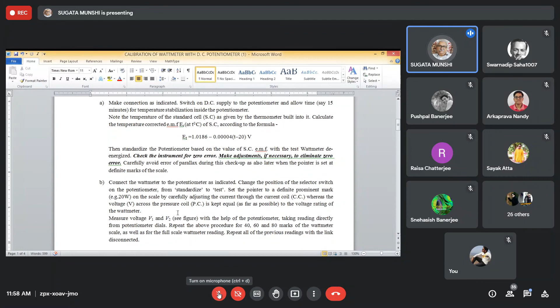Then what you have to do, you have to give the calibration plots. How do you compute the errors? W0 minus WT, observed wattmeter reading minus true wattmeter reading, divided by full scale reading of wattmeter. Full scale reading of wattmeter is 100 watt here. Just see that here the reading starts from 0 wattmeter reading - we have ensured that all these values, they are 0.